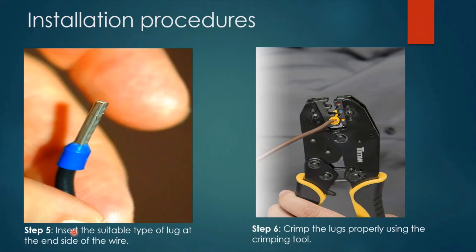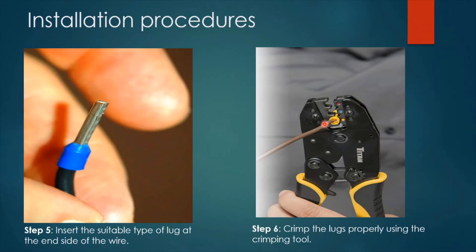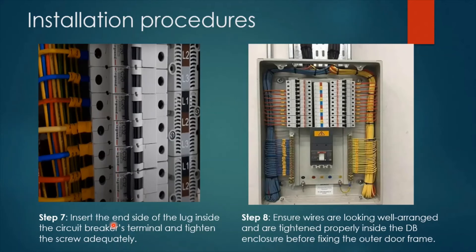Step five is to insert the suitable type of lug at the end side of the wire. Step six is to crimp the lugs properly using the crimping tool. Step seven is to insert the end side of the lug into the circuit breaker's terminal and tighten the screw adequately. This is exactly what is meant by termination — inserting all the wires into the assigned circuit breakers according to the DB schedule.